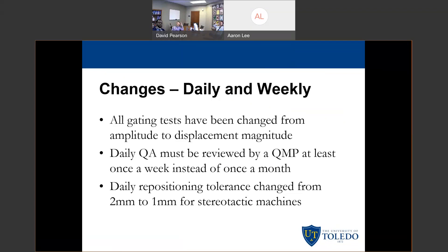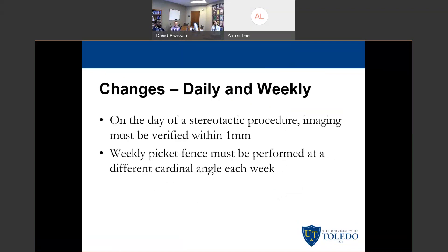They highly recommend that daily QA be reviewed every day. They also said the daily repositioning test tolerance has to be changed from 2 mm to 1 mm for stereotactic machines; for a regular non-stereotactic machine, 2 mm is still sufficient. On the day of a stereotactic procedure, imaging must be verified within 1 mm — a Winston-Lutz on the day of SRS is sufficient and is specifically named as a way to validate your chain. The weekly picket fence must be performed once a week at a different cardinal angle each week — you cannot just do G0 or G90 every single week; you have to do it on a rotating schedule.